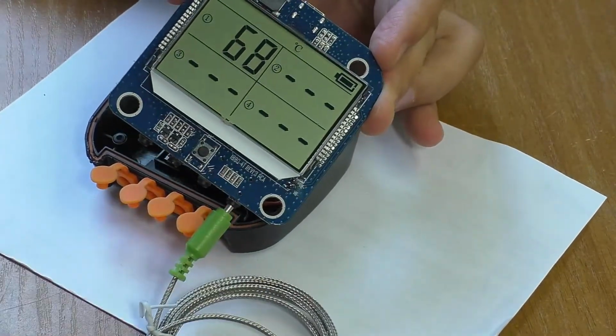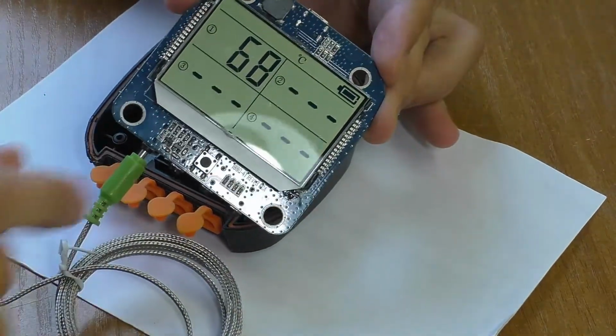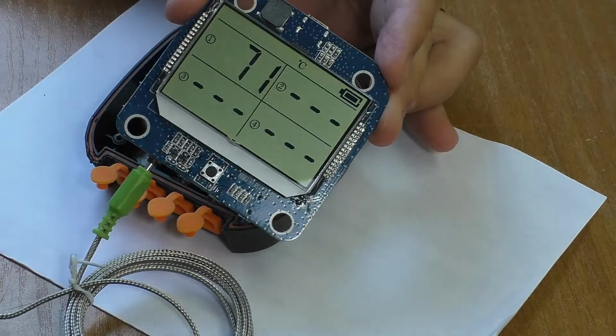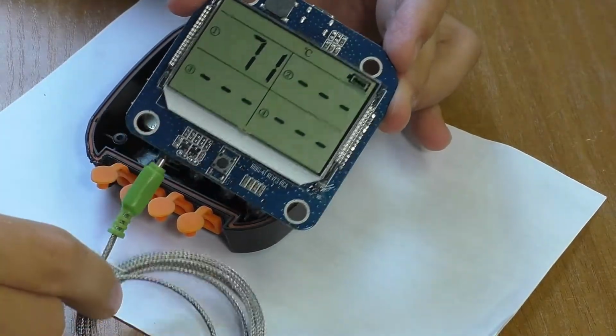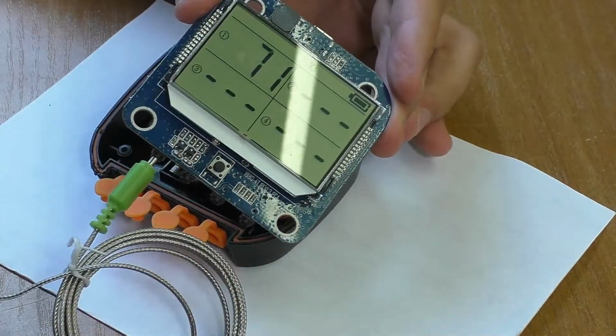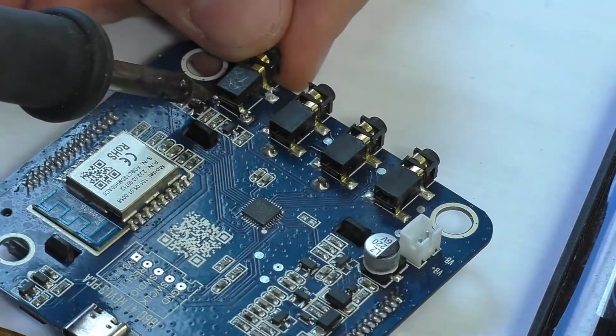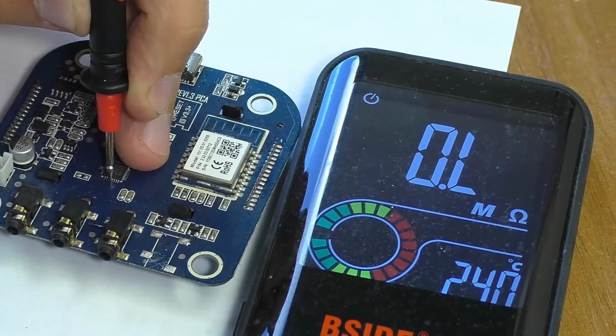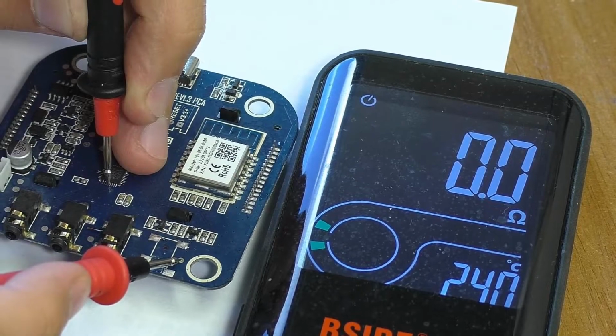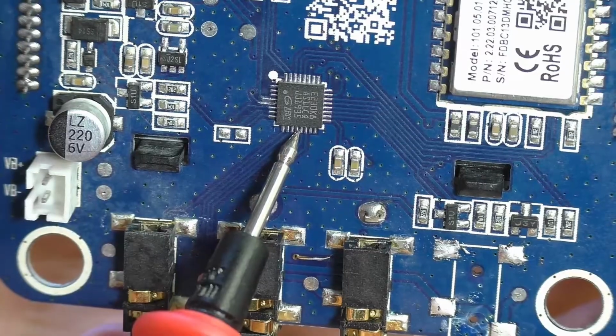Checking the connectors for thermometers. All work except one. On it, even without a sensor, the temperature is about 70 degrees. Something happened to the first channel. I checked connector 1, everything is fine with it. Everything is also fine with the tracks. The signal from the connector immediately arrives at this microcircuit.